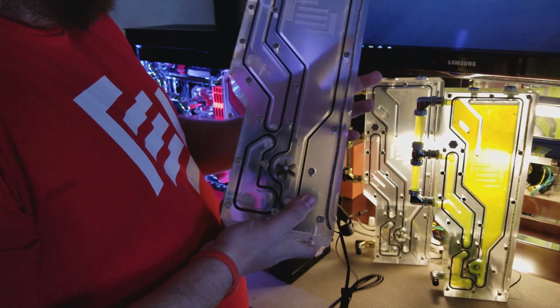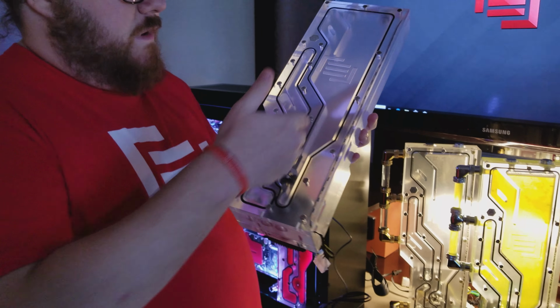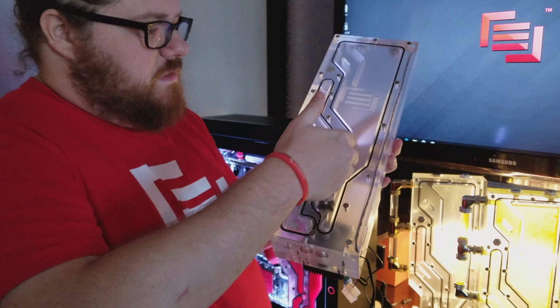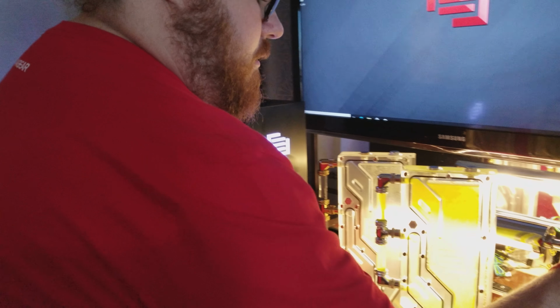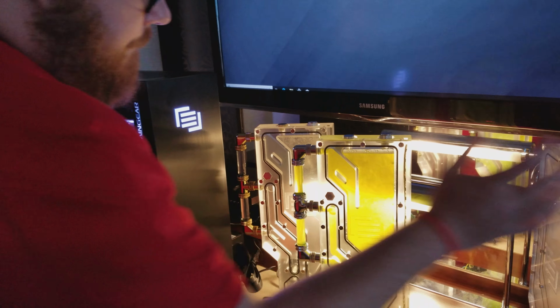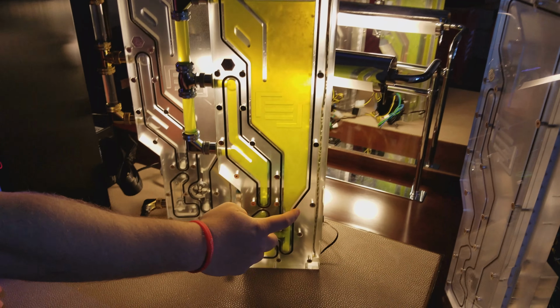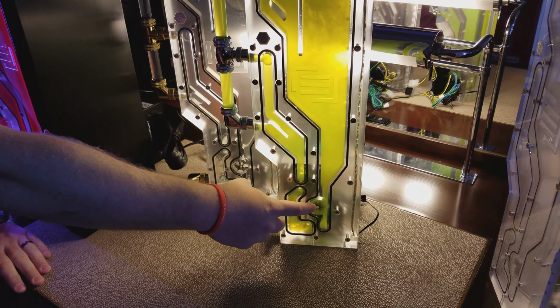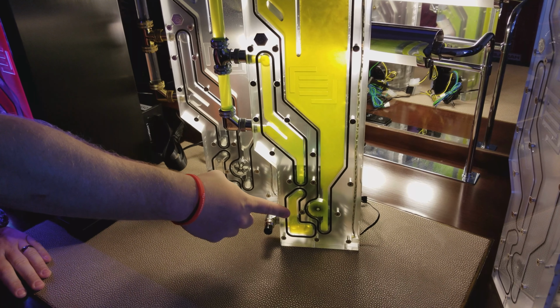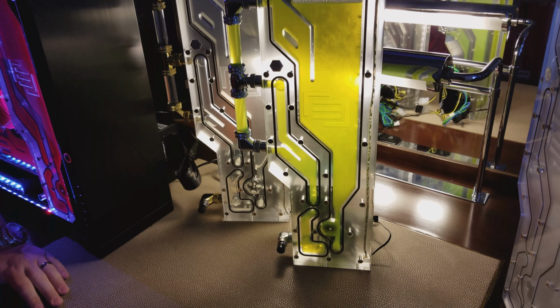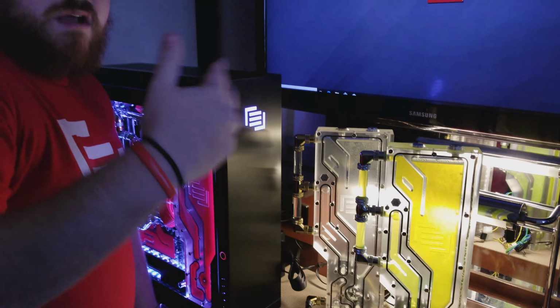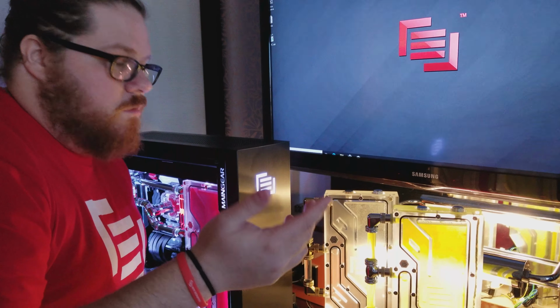The block itself is parallel, pressure regulated. Essentially, the coolant comes in — it's easier to show you on the one with the liquid inside. The coolant is pumped down through here, goes through a flow meter. There's a temp probe that allows us to adjust the speed of the fan and pumps based on coolant temperature instead of just load, which is really awesome.